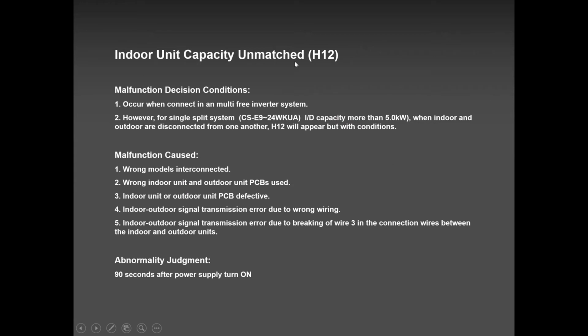H12, you remember I mentioned to you H12, it's the wrong indoor unit that got installed. Okay, wrong indoor unit, a single zone got put into a multi-zone. But very rare H12 will happen. Or you are under capacity. You remember I told you you can put 2 indoor units on a multi-zone as a minimum amount of indoor units. However, you need to respect the minimum and maximum capacity. So please keep in mind that you need not only to put 2 indoor units, but also you need to watch for the capacity. And if you don't obey that, you might end up getting H12.